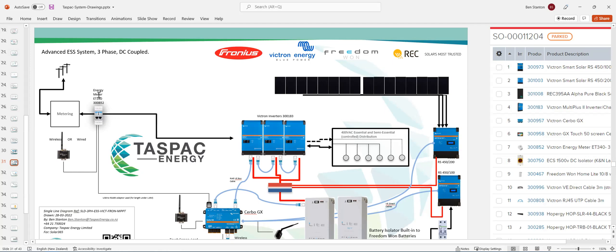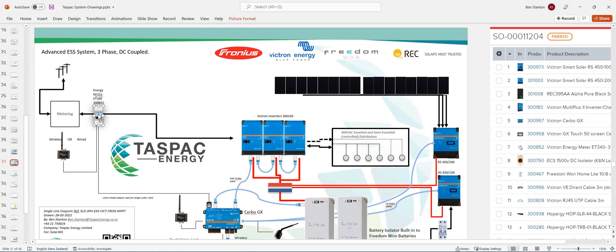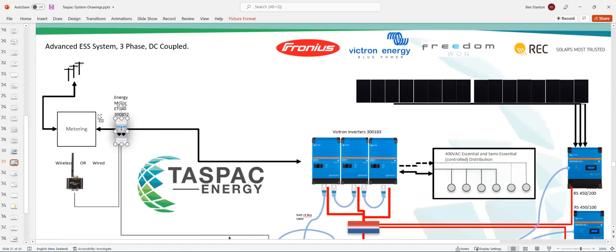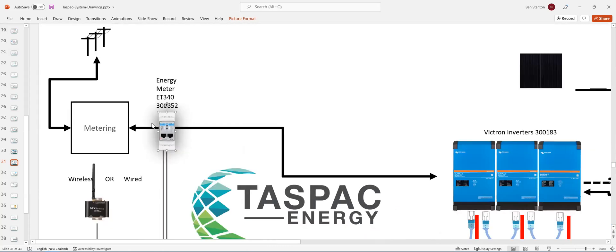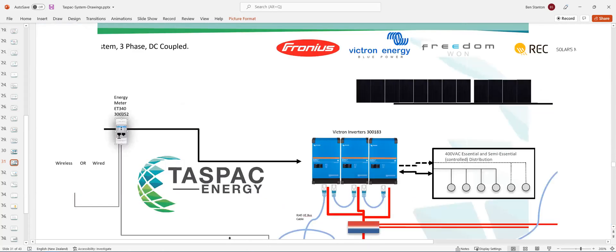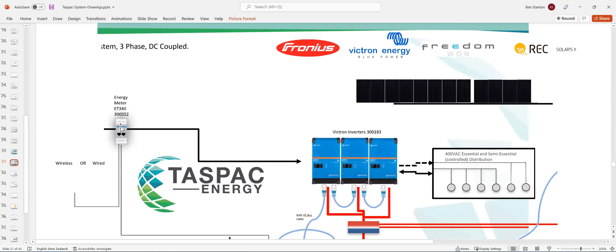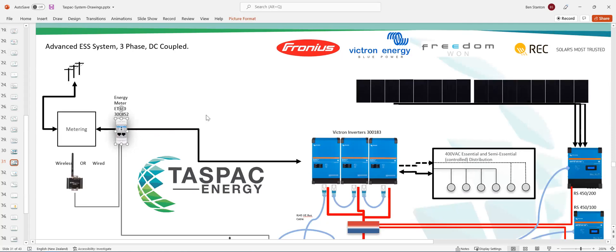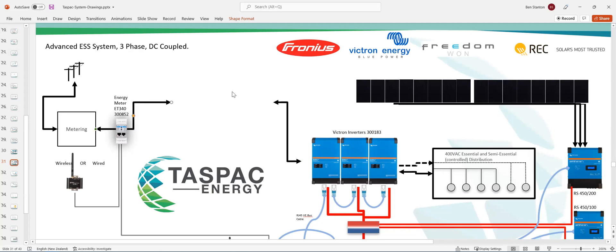Now, the energy meter is a three-phase energy meter. Just put the three phases through it. And that needs to be at the meter. Well, not necessarily right at the meter, but before any load.